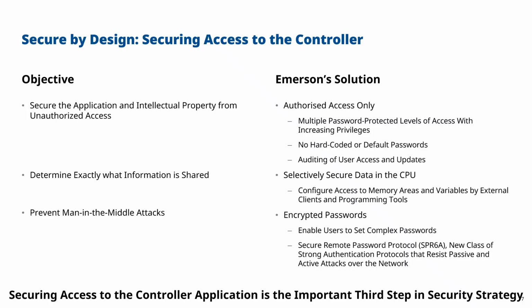As well as authorizing access at the higher level of the CPU, we can also authorize individual access to function blocks. So within the PLC code, if there is a piece of, say, analytical routine that you want to protect, you can separately protect that either from being viewed or read, and that can either be password protected or permanently locked. So there are options there for additionally protecting intellectual property if you're an OEM with proprietary routines.